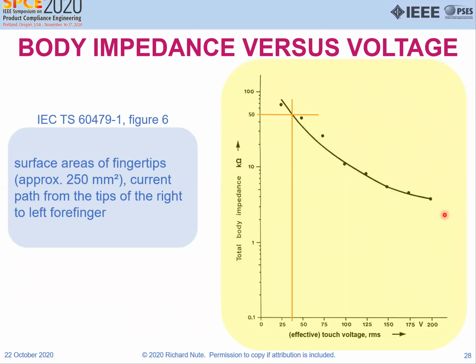Here's the curve taken from 479, figure 6. Surface areas of fingertips, current path from the tips of the right to the left forefinger. And this is what was measured on one body. This is touch voltage in this direction and body impedance this way. And if we enter the voltage that we measured, 34 volts peak, is 50,000 ohms.